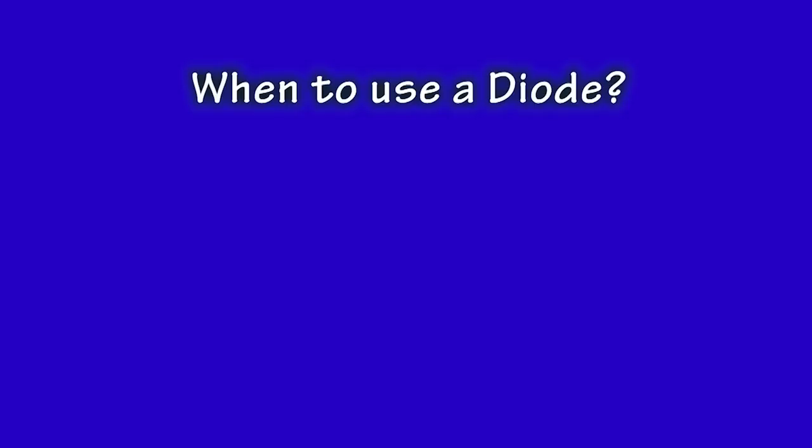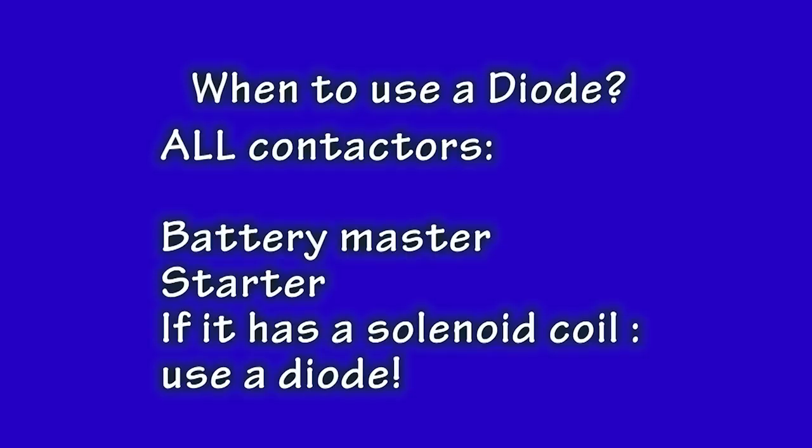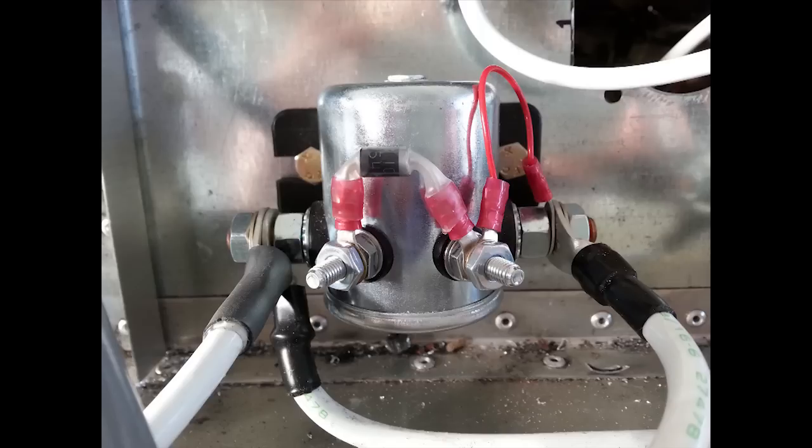To summarize, from our Department of Sweeping Generalizations, when using any contactor, whether it is a battery contactor or a starter contactor, any time a coil is involved, use a diode wired across the coil.